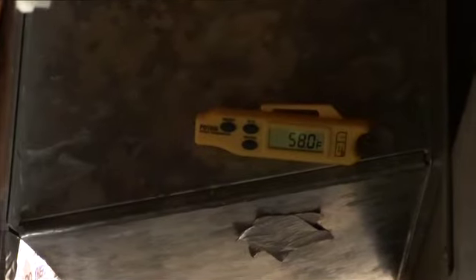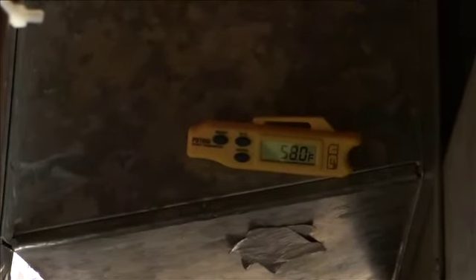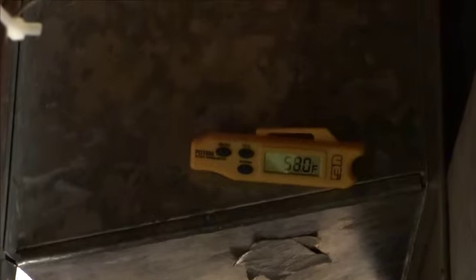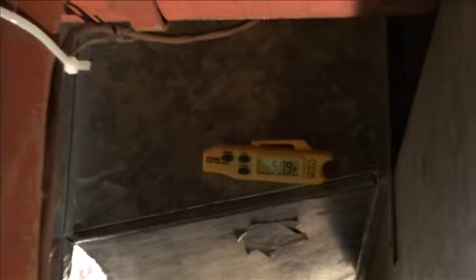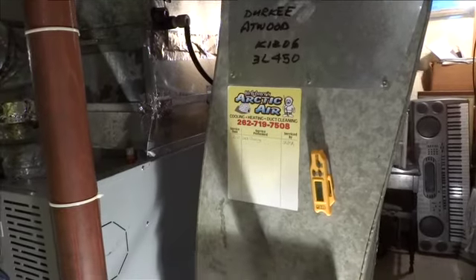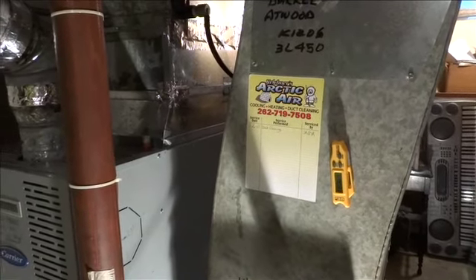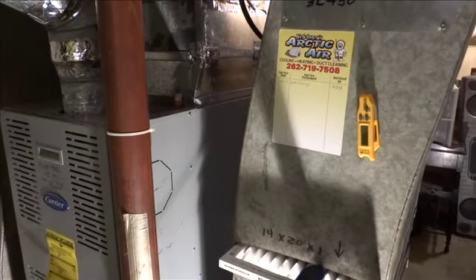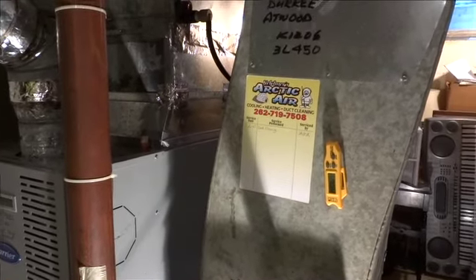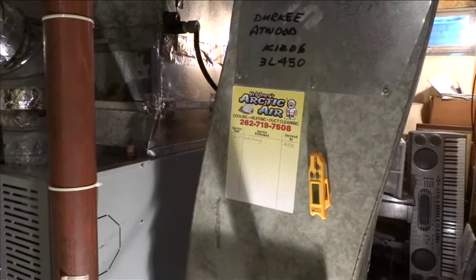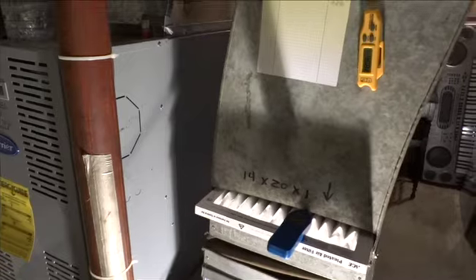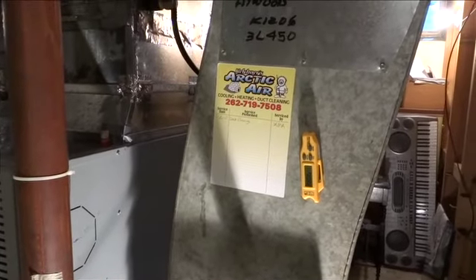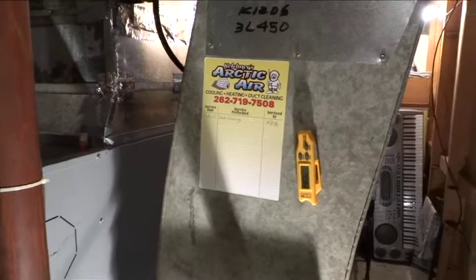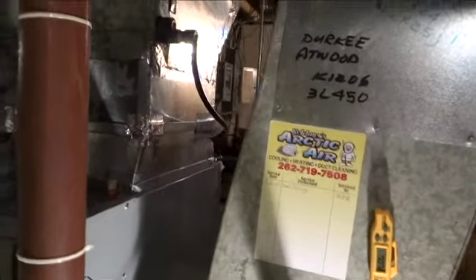This is a thermometer stuck in the supply side of your ductwork, so we take the reading from that, and then we take the reading from the return side here. Same thing, there's another thermometer in there. You want anywhere between 15 and 20 degree temperature difference. If you're under that, you possibly could be a little low on Freon. I think we're right at about 13 degrees, so that's a little less than we want to see.